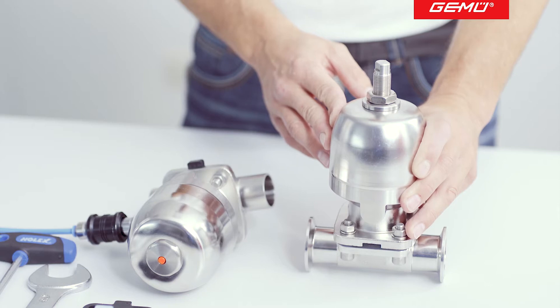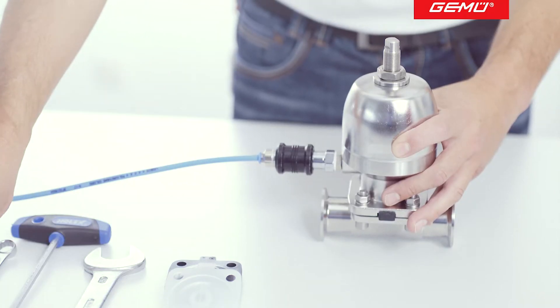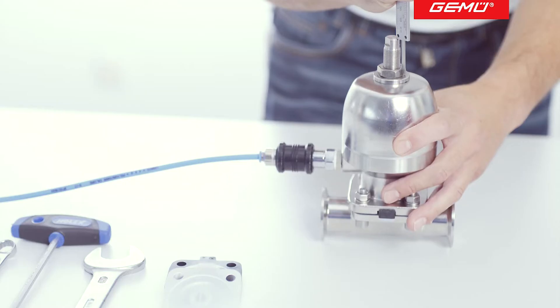The limiter must be removed before replacing a diaphragm. Before removal, we advise that you measure the installation length of the opening limiter as a point of reference to facilitate subsequent refitting. Now loosen the lock nut using an appropriate tool and dismantle the opening limiter.